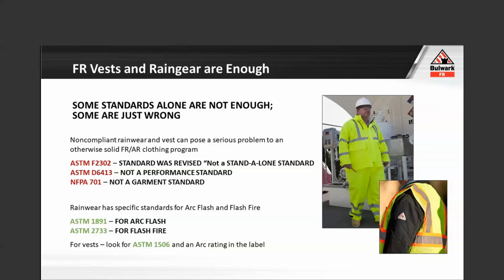That wasn't even a garment standard. It's a drapery and linen standard, primarily for the hospitality industry, and it was misused, again, for rain gear and vests for many years. But if you have some older inventory and you see that one on there, that again is not designed for your hazard. So what is designed for your hazard? Typically for vests, we're going to see ASTM 1506 and an arc rating in that label, or you're going to see NFPA 2112 compliant for a vest. For our rain gear, we want to see ASTM 1891 for arc, and we want to see ASTM 2733 for flash, or both. Ideally, both.